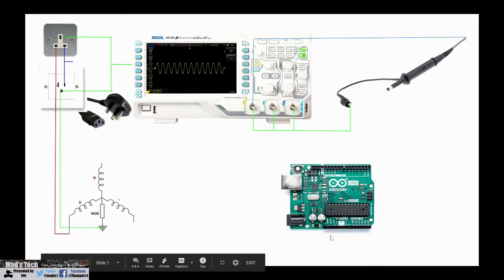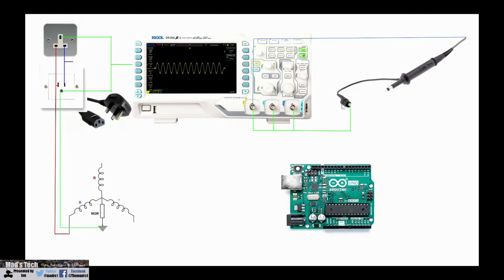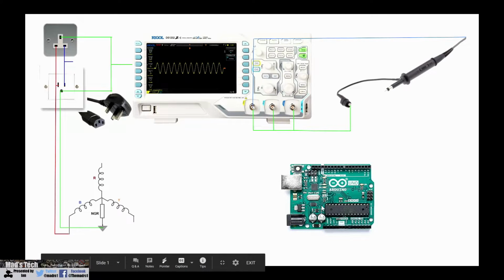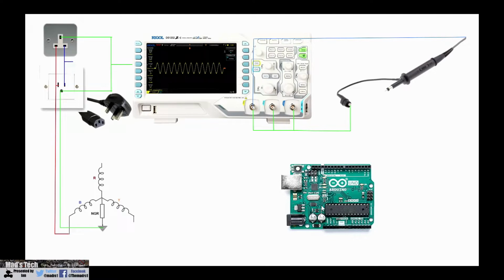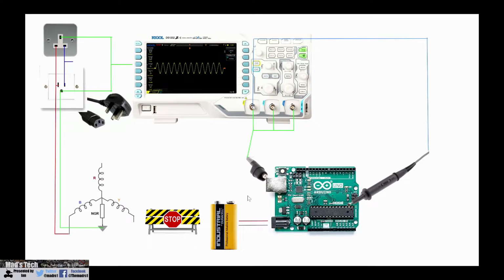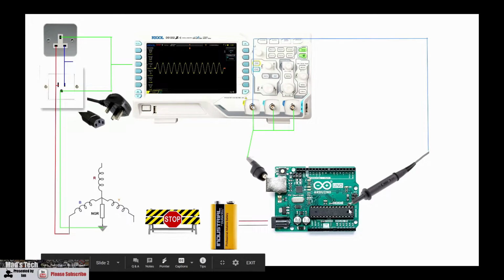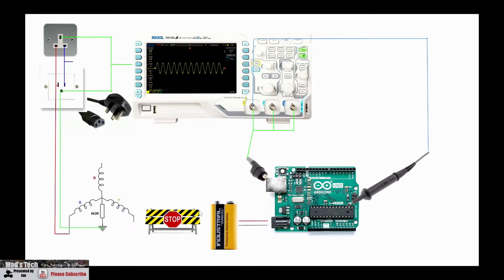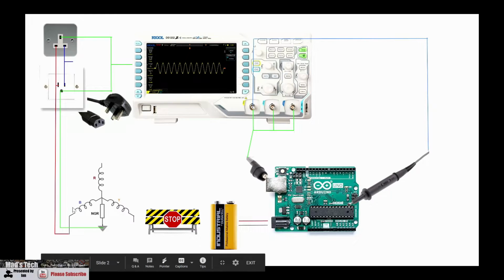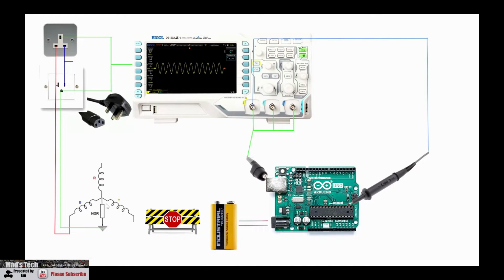Now, when you are working on battery devices, things like an Arduino, a battery product, and you're testing signals and voltages, the reality is wherever you clip this probe really doesn't matter too much, because you are only referencing that device to the earth of your property. This device is not plugged into the mains. It has not got its own potential in relation to the mains, so there is nothing to be concerned about. Now, just showing the demo circuit of this, we have a battery powering the Arduino. We're testing a signal off the IC, and because there is no reference between this battery and this mains, because the earth probe is connected to the earth shield in here, everything is fine, because there is nothing to link this circuit back to our main circuit or our mains transformer.